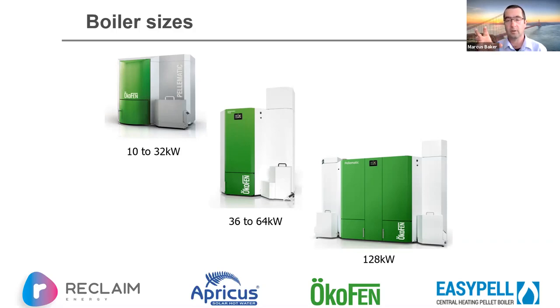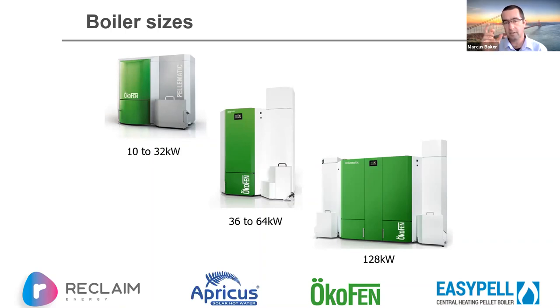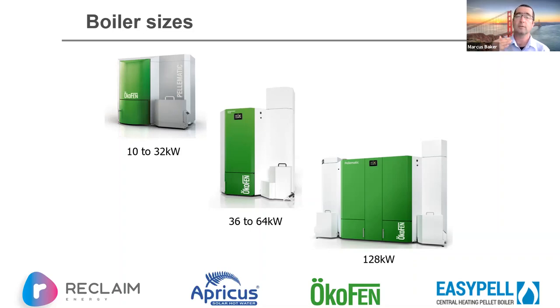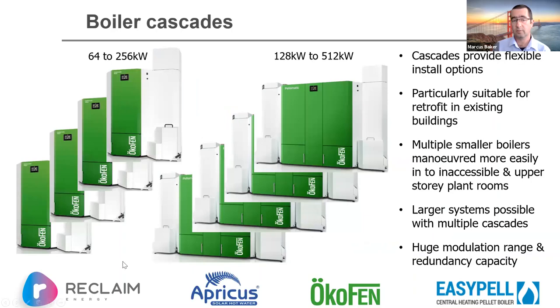Some other boilers go up to a larger capacity in a single unit — the biggest I saw was 260 kilowatts. Above that size it stops being a practical single pellet boiler unless you're making a bespoke industrial one, because all the details about combustion phases, good control, and safety become very difficult above 250 to 260 kilowatts.